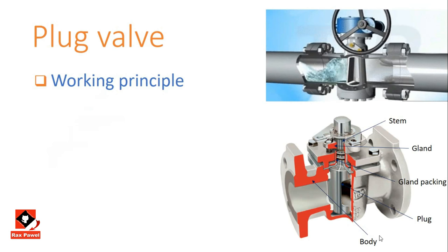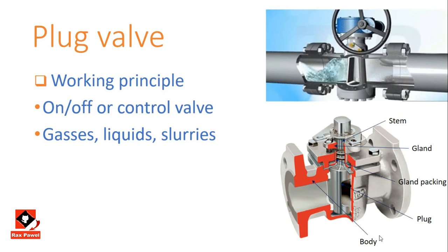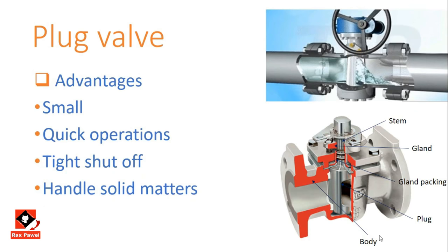Plug valve working principle: it has a plug connected to a rotating stem. It can be used as an on/off and control valve while handling gases, liquids, and slurries. Advantages: the plug valve is smaller in size, allowing quick operation, has good shut-off capability, and can deal with fluids containing solid matter. Disadvantages: if operated quickly it requires higher torque, and the cost of the plug valve is higher.